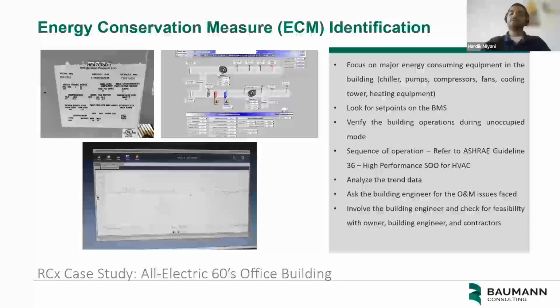Interestingly, there were certainly a few pieces of equipment that were operating for a longer time. There were a few set points, like the nighttime setback, that were still operating at a very high temperature during unoccupied mode. And there were a few sequences of operation that were not as per the original design intent.